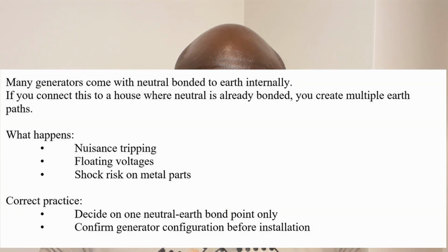Generator neutral bonded incorrectly. Many generators come with their neutral already bonded to earth internally. Okay, if you connect this to a house where neutral is already bonded, you are creating multiple earth paths. Now, what happens in this scenario is that you can get a lot of nuisance tripping, breakers tripping when they're not supposed to trip. You get floating voltages. You get electric shock risk on metallic parts.